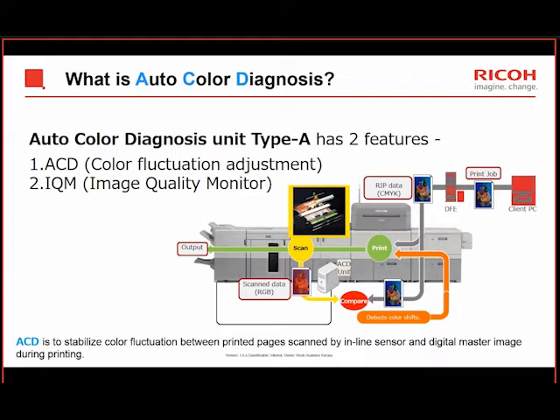And then we have an image quality monitor, and the image quality monitor is there to check for any defects. So things like white spots, white lines, black spots, anything like that, the machine will check for, and then it will tell the customer if there's a problem with one. And I think I have a better slide to explain how it works in a minute.